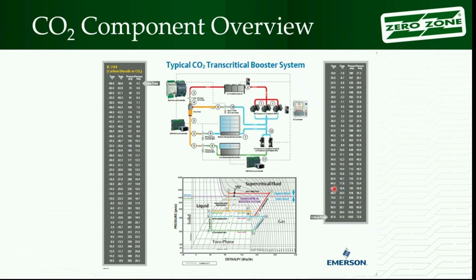But something to keep in mind, notice the chart ends at 87.8, about that 88 degrees. You get above that point, you're in transcritical mode. There is no temperature pressure relationship anymore. That doesn't exist. So now when I'm down lower here, if I have liquid in a pipe and I can measure the temperature of the liquid in the pipe, I know what the pressure will be when I put a gauge on it. It matches across this. Get above that, measure the temperature, the only way you're going to know what that pressure is, you have to put a gauge on it. You can't predict it, can't look it up on the chart.